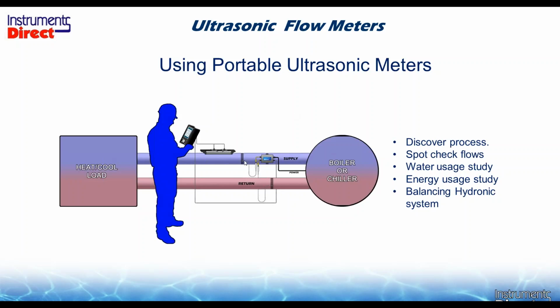We would add temperature to the supply and temperature to the return. Now, the first thing you need to get away from is the actual temperature of the liquid. These are clamp-on high-precision RTDs. When they're matched pairs, they're calibrated better than 1%, and much better than 1%. In this case, they will be a few degrees different from the process temperature inside the pipe, but that's not part of the equation.